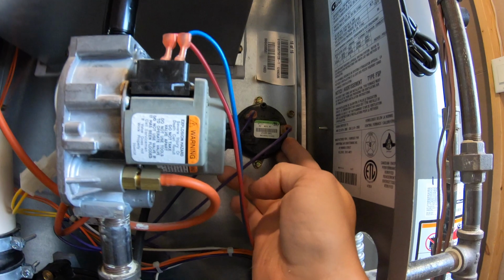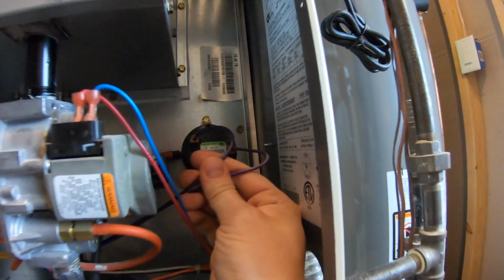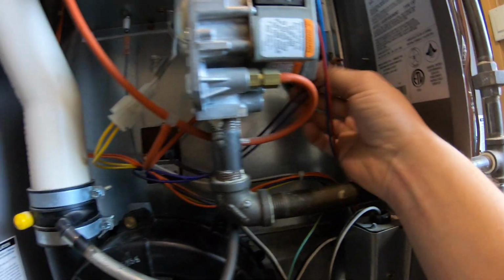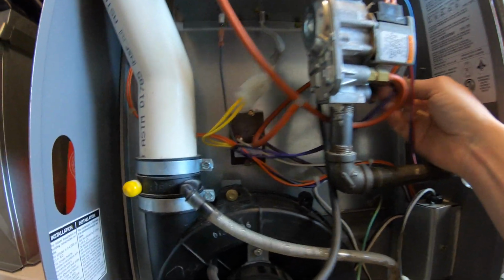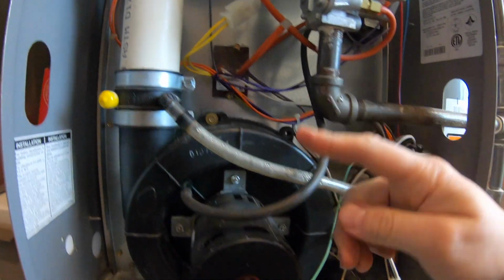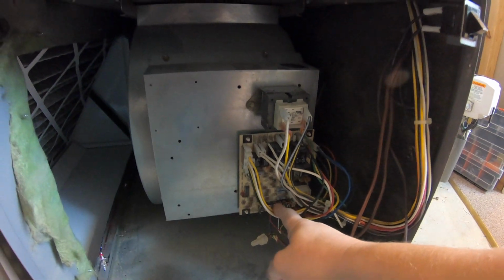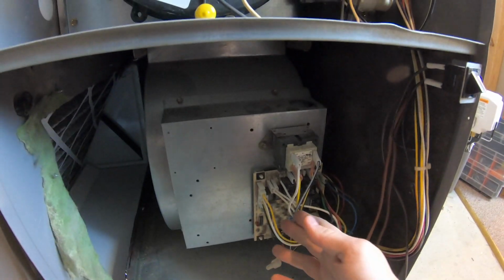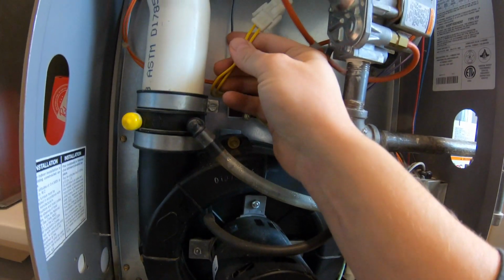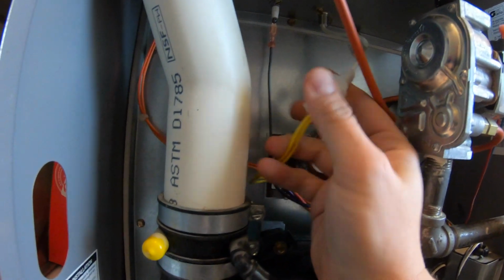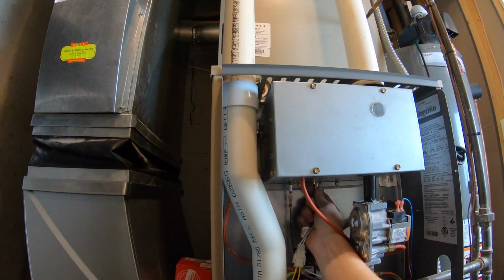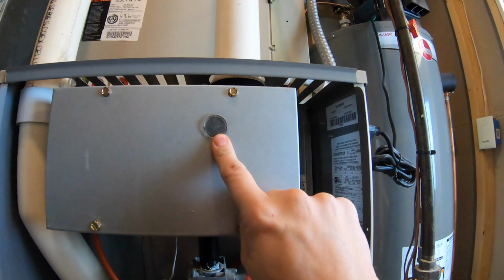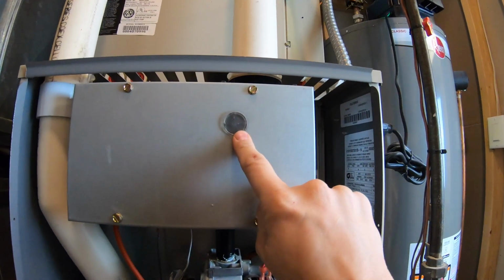Once this pressure switch is closed, it tells it through this circuit here, these two purple wires, that that switch is indeed closed. It sends that power back down to the circuit board, which says, all right, pressure switch is closed, time to start the furnace. So that sends power, 120 volts this time, to these wires here. This is for your igniter, these two wires going up into the burner compartment. You'll see through this little peephole here, an orange light glowing.